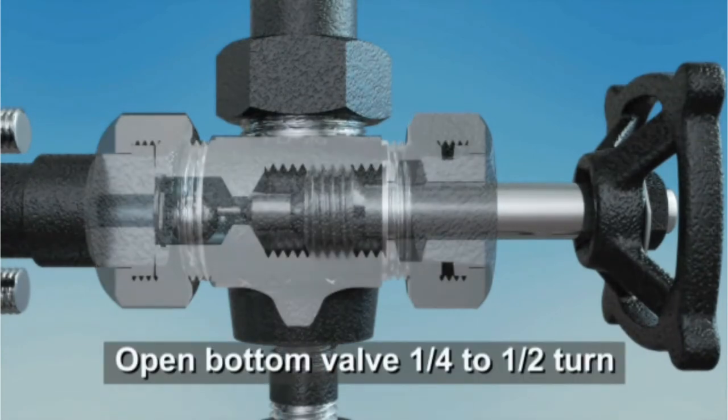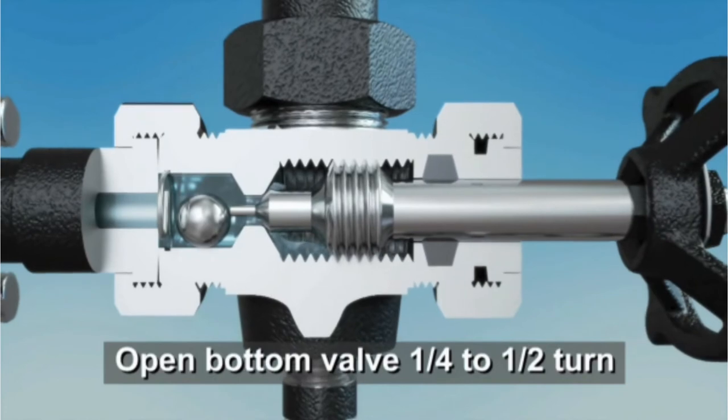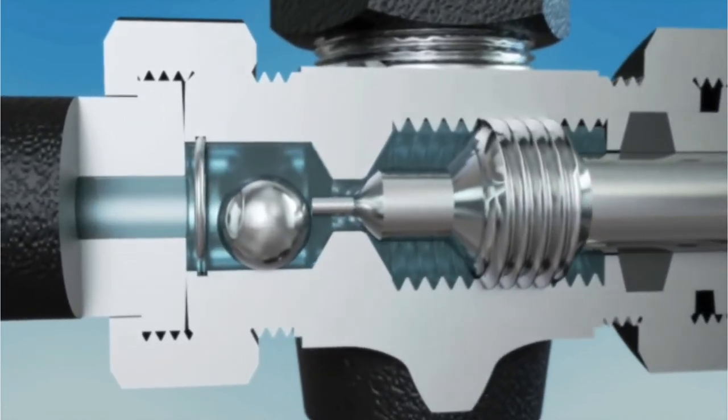Next, open the bottom valve one-quarter to one-half turn to allow liquid to flow into the gauge. Notice how only slightly opening the valve keeps the stem tip in contact with the ball check. The importance of this will be explained shortly.